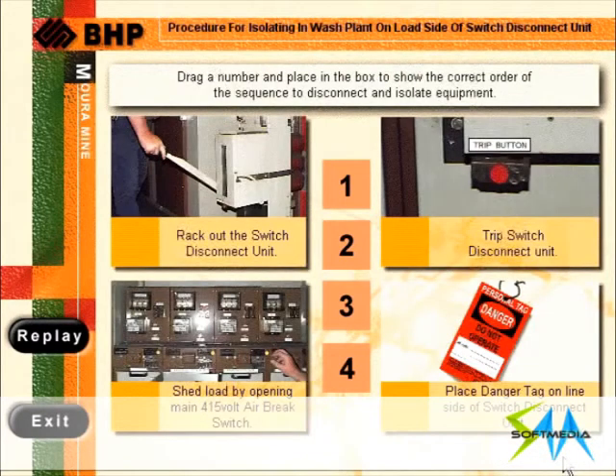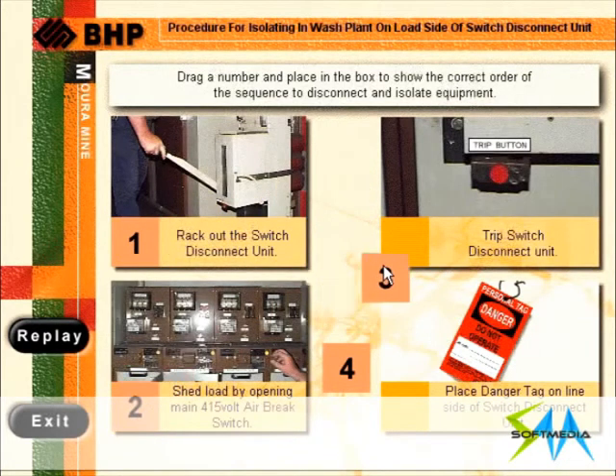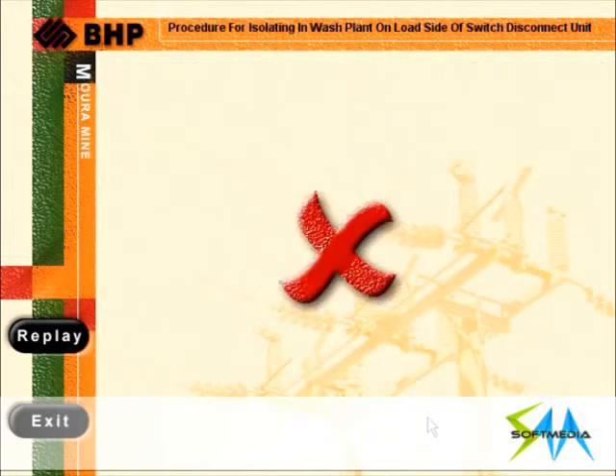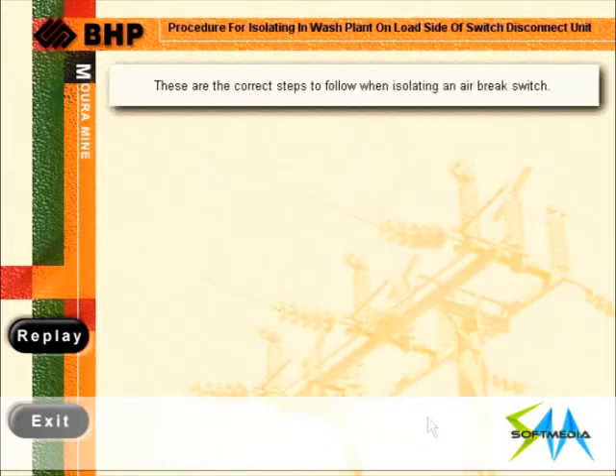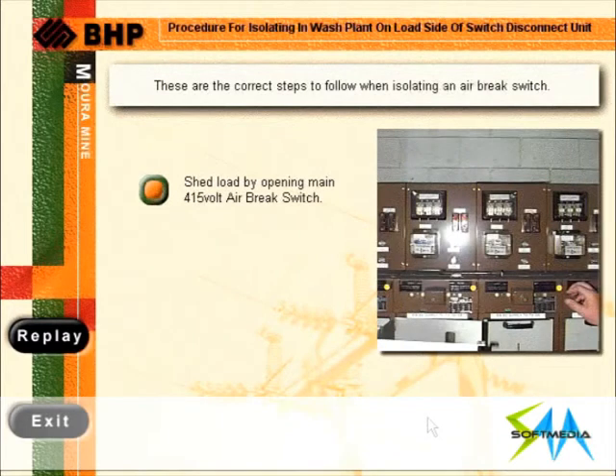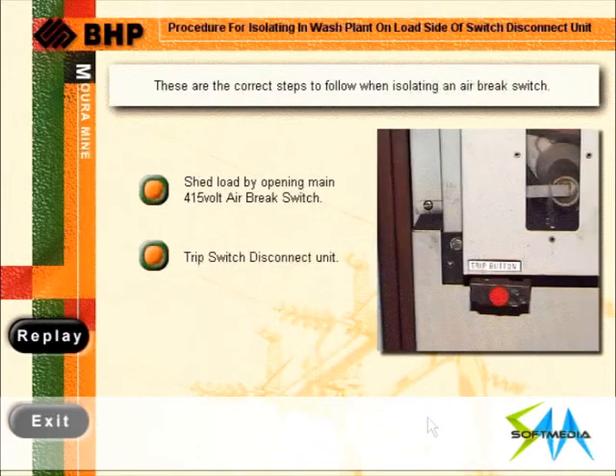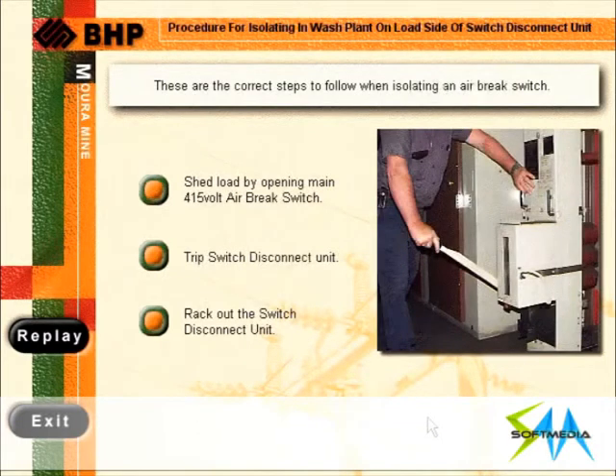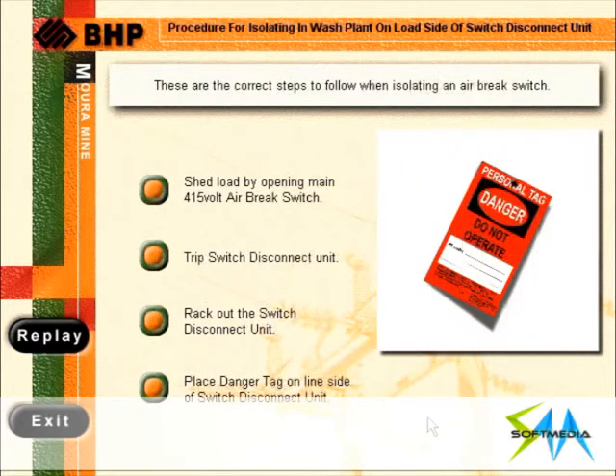Drag a number and place in the box to show the correct order of the sequence to disconnect and isolate equipment. That's incorrect. The correct sequence of steps to disconnect the switch disconnect unit to isolate equipment is shed load by opening main 415-volt air break switch, trip switch disconnect unit, rack out switch disconnect unit, place danger tag on line side of the switch disconnect unit.